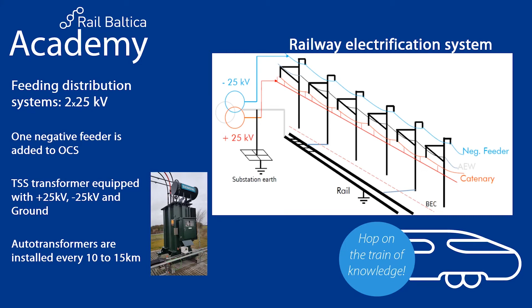We have this quite interesting situation with the current. If we look at where the train is located, on the right side of the picture you have one auto transformer center, and another one just in front of the train. The train is actually fed from both sides of the catenary: a quarter of the current is coming from the auto transformer, and three quarters of the current is coming from the left side, from the auto transformer closest to the substation.